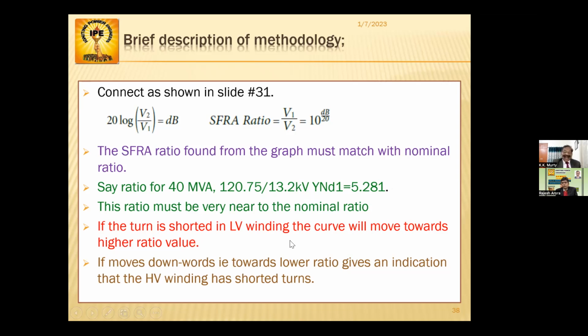If you remember, in any transformer, the turn ratio is such that the LV winding has fewer turns and the HV winding has more turns. So the LV winding curve will move towards a higher ratio when the LV winding is shorted. When the LV winding is shorted, LV winding is in the denominator. If it is shorted, the number of turns is less. So naturally, the resultant will be more.